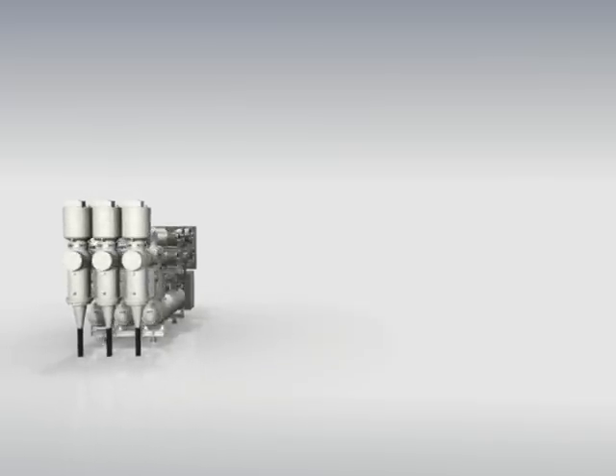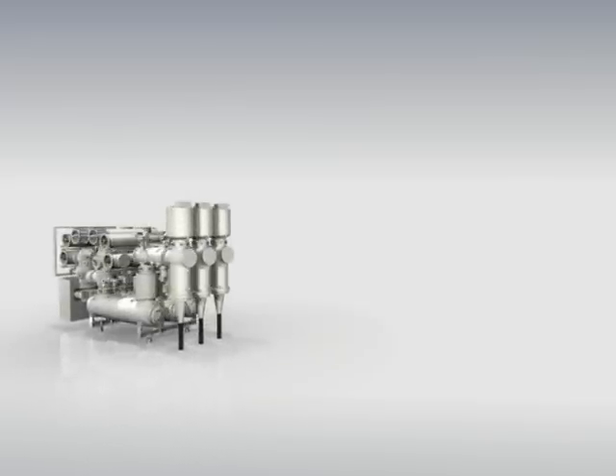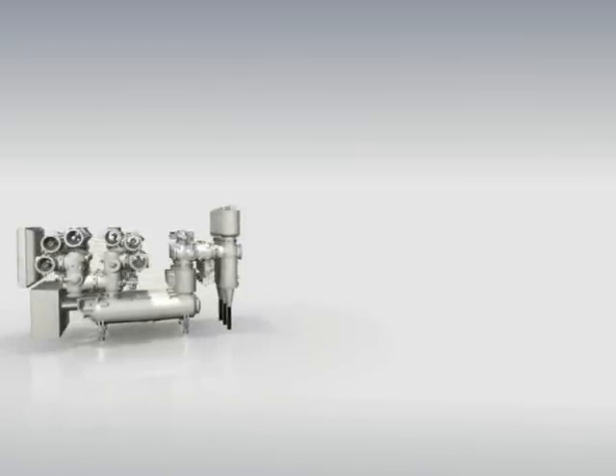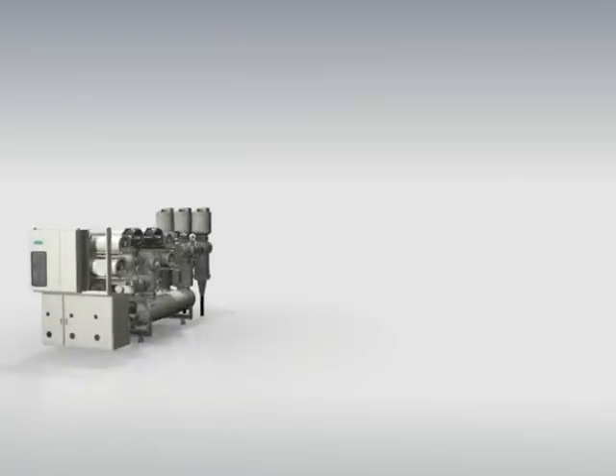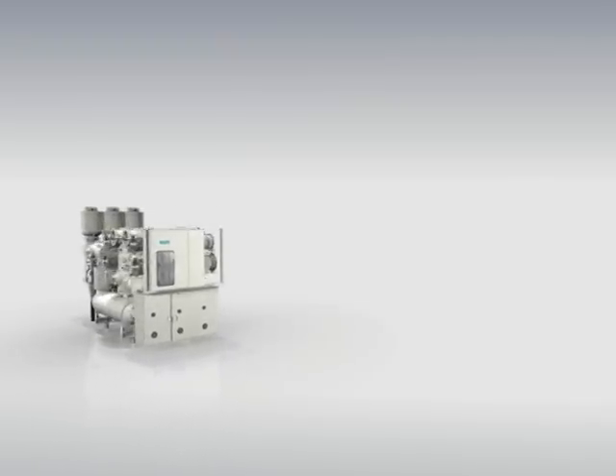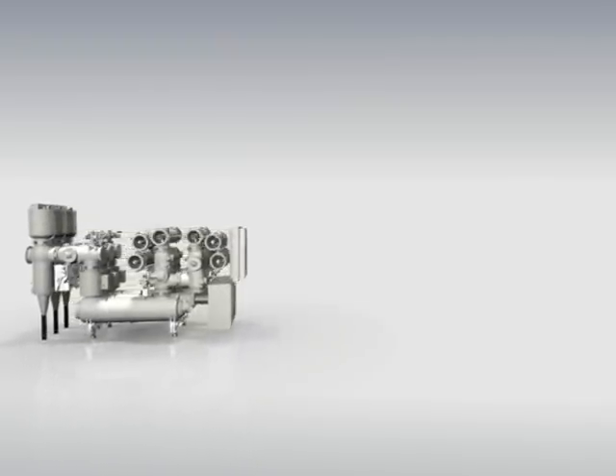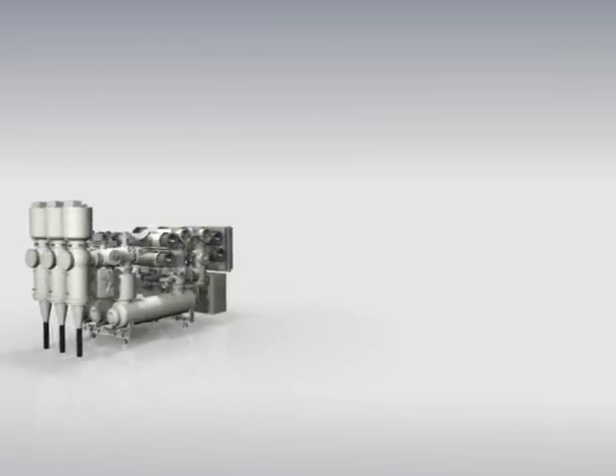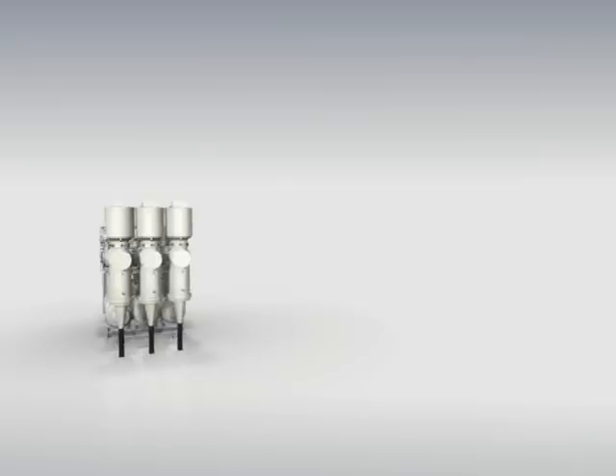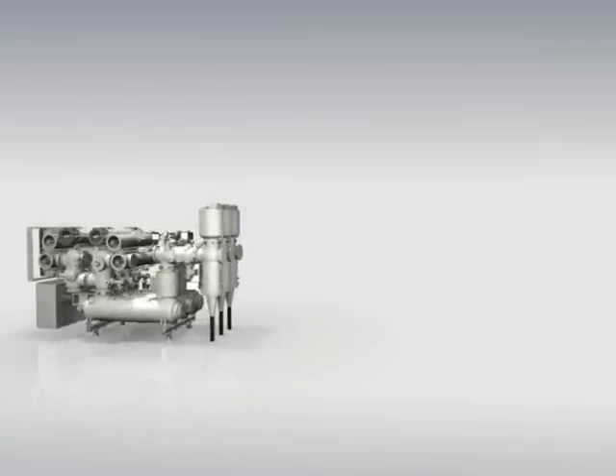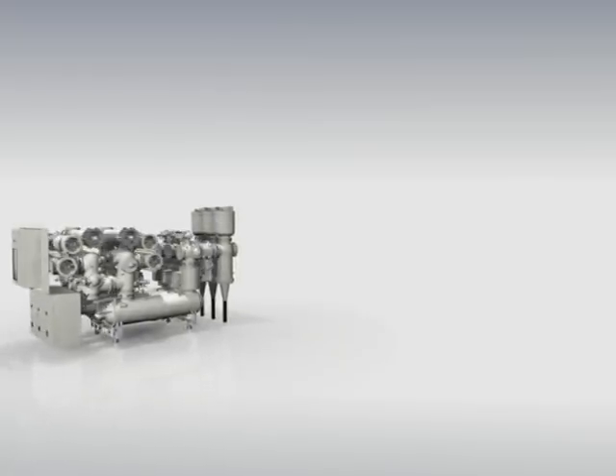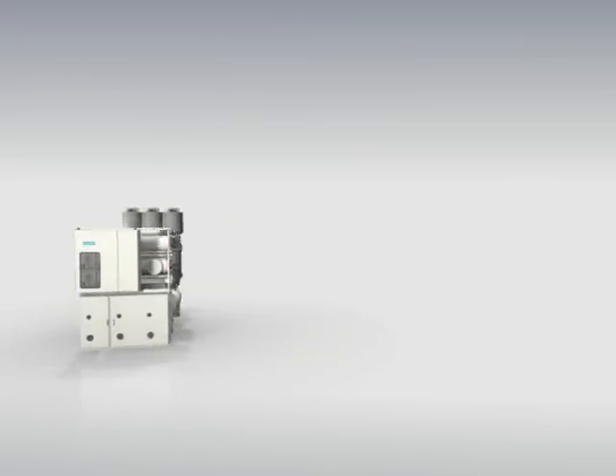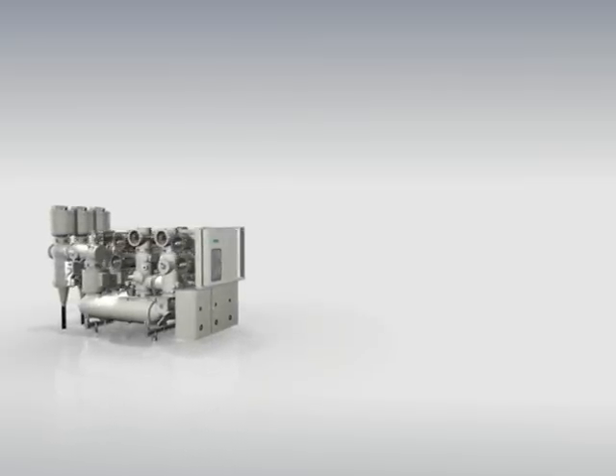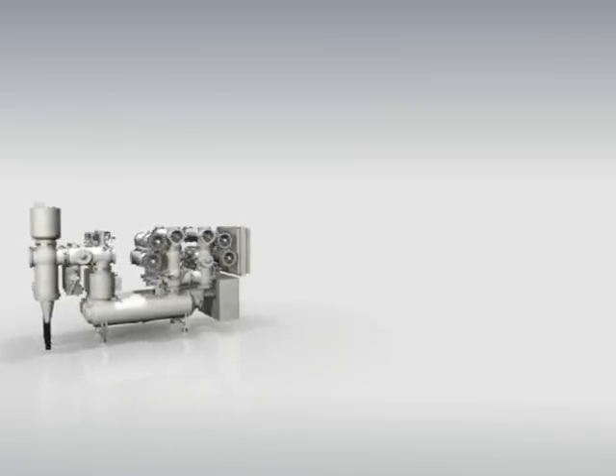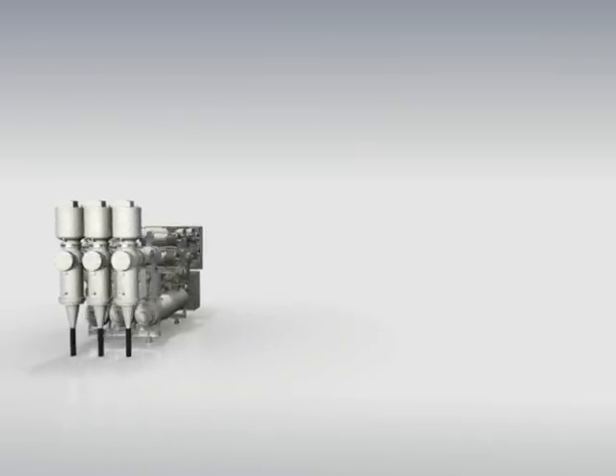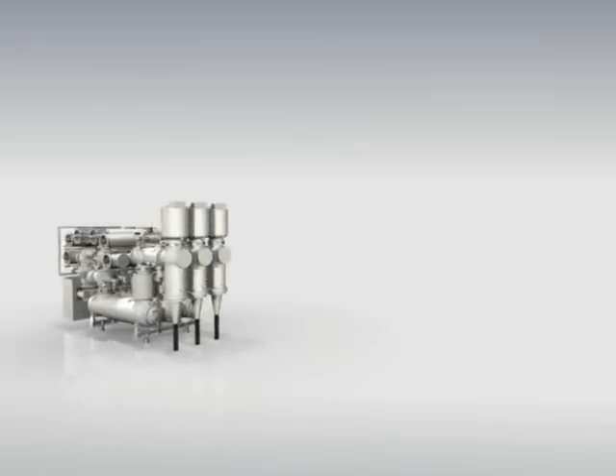short erection and commissioning time due to completely pre-assembled and pre-tested bays, its high degree of gas tightness, which provides for environmental friendliness, almost negligible maintenance, its long service life, low life cycle costs, type approval and certifications to the latest IEC and IEEE standards. Like every other Siemens gas-insulated switchgear, the 8DN9 switchgear is certified to the latest ISO 9001 and 14001 standards. It is type-tested according to the latest IEC and IEEE standards at independent testing laboratories.